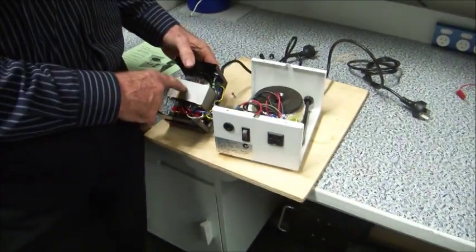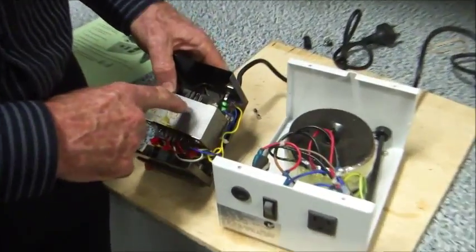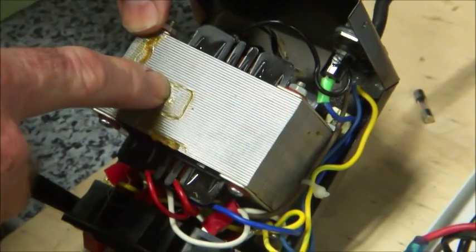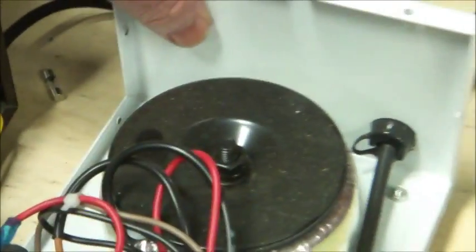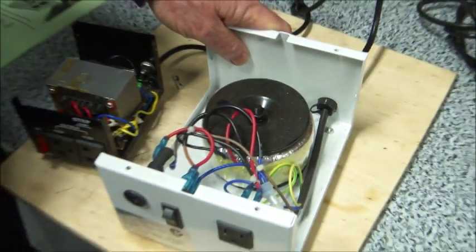The other thing you might want to see is that there is no way that this transformer is capable of doing 200 watts. That's only a 100 watt transformer, it hasn't got a continuous rating. This transformer is continuously rated 24-7 and will meet the requirements.